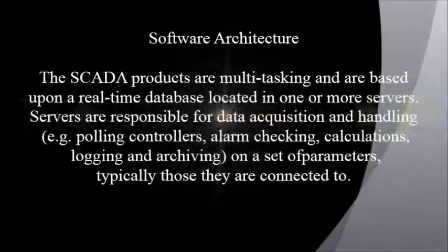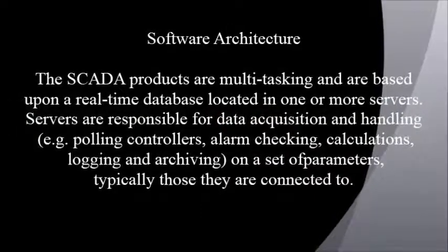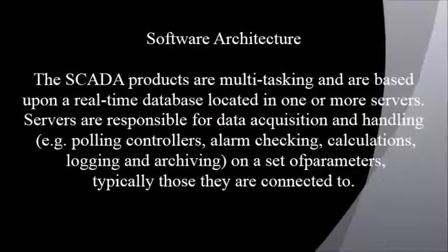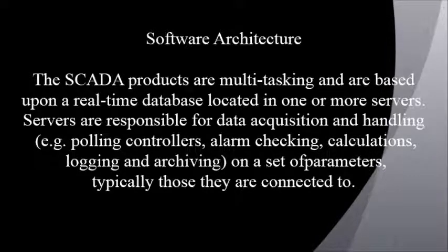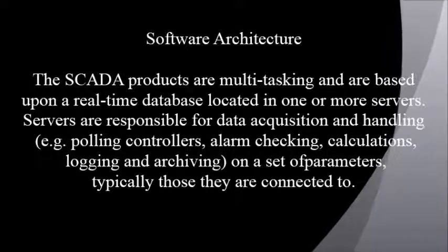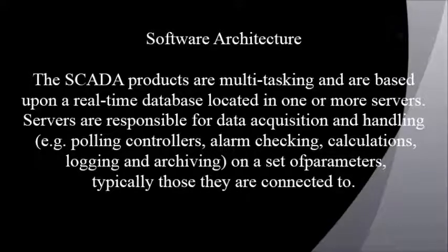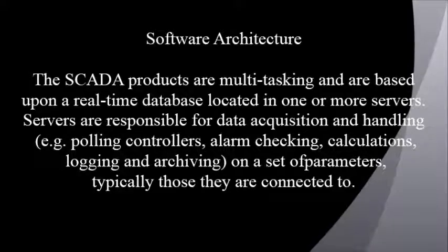Software Architecture. The SCADA products are multi-tasking and are based upon a real-time database located in one or more servers. Servers are responsible for data acquisition and handling — for example polling controllers, alarm checking, calculations, logging and archiving — on a set of parameters, typically those they are connected to.